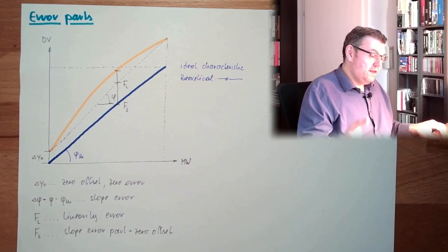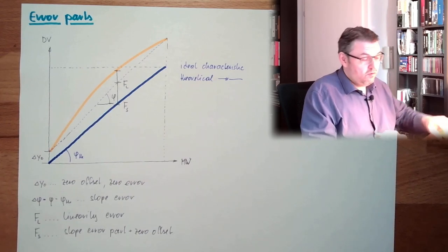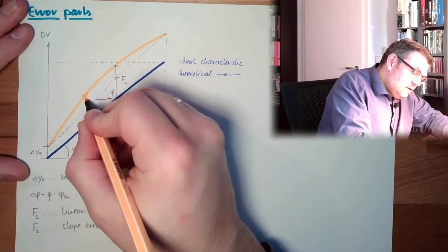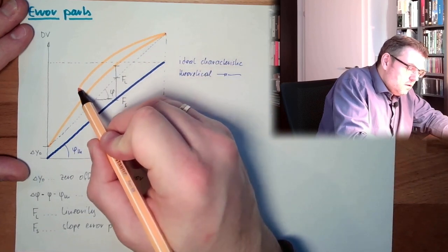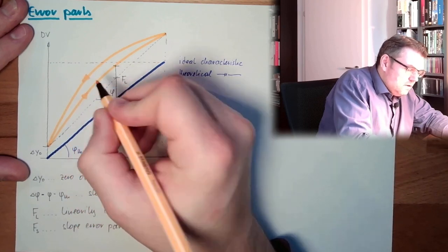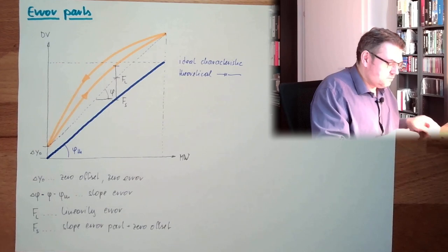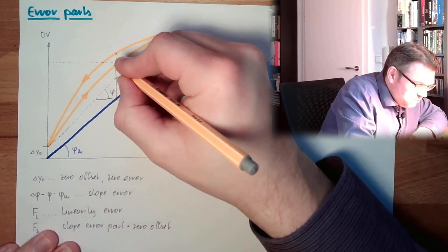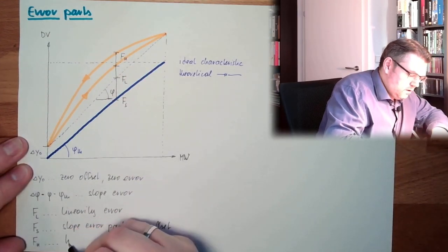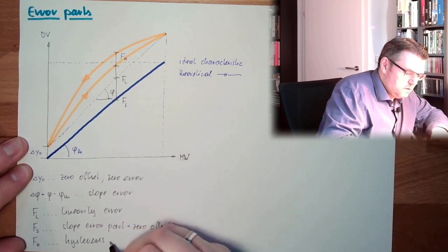And then we might have the situation, or often have the situation, that we are not having one line, but one line for rising values and another line for falling values. So then we also have here a hysteresis error.